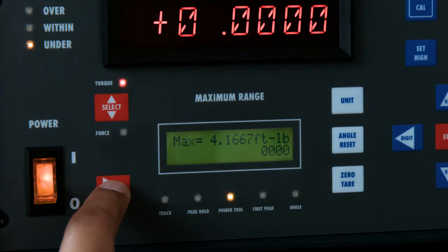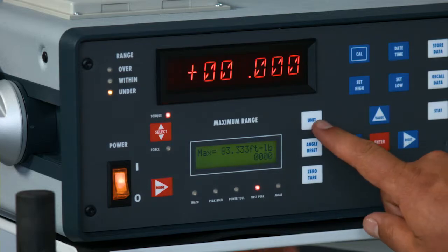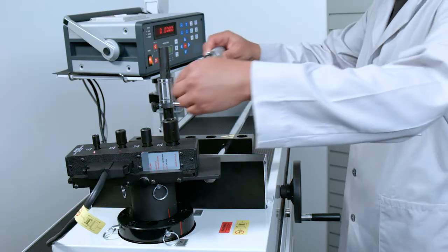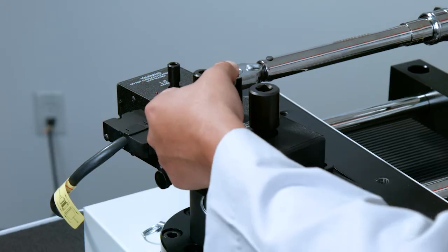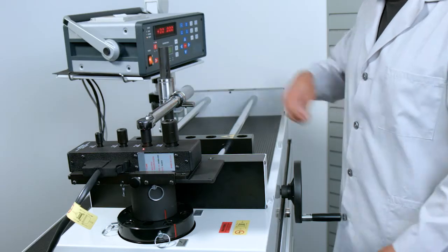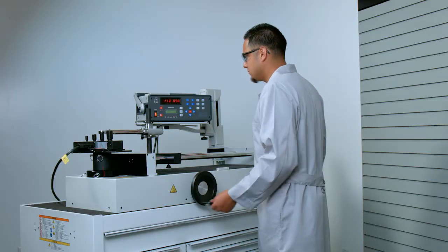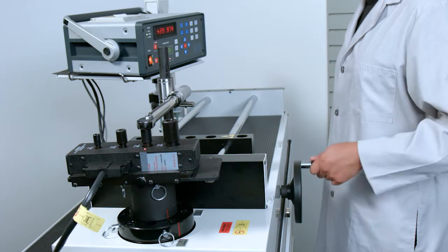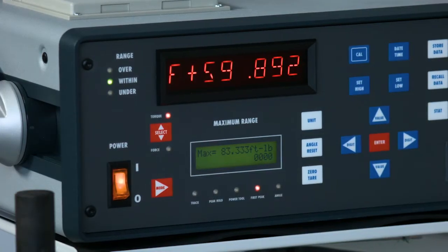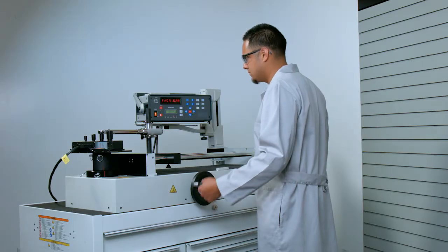To calibrate a torque wrench, first select the correct mode and units of torque on the monitor, select the correct torque transducer, and then mount the torque wrench. Turn the gear reduction handwheel to rotate the transducer, thus applying force to the torque wrench. The system detects the first peak of the wrench and stores the reading automatically.